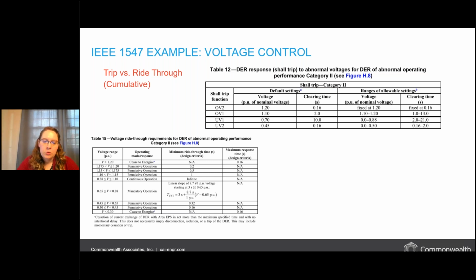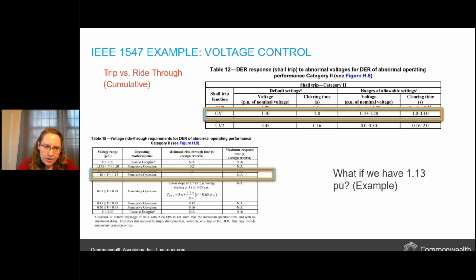Previously, IEEE 1547 had a shall trip requirement for most abnormal conditions. That was the 2003 version of that standard. But in the intervening years, the philosophy has changed. So now in the latest standard by IEEE 1547, there are some cases where voltage ride through capability is required. So the batteries must be capable of riding through no matter what. And there are other times where they have to be capable of regulating voltage. But much of that is on the operator to determine exactly where those ranges will fall.